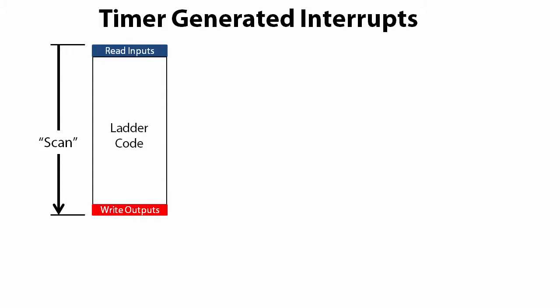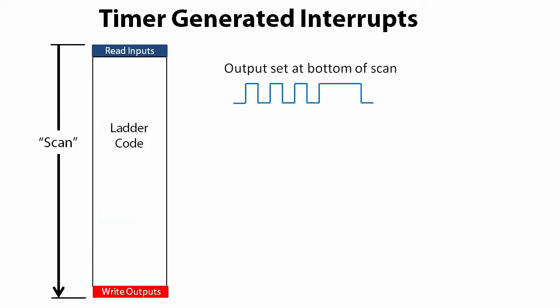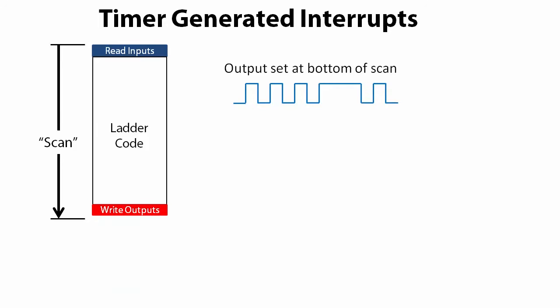If we toggle an output bit every scan, it will look like this on most scans, but on some scans it might take a little longer. It all depends on what the ladder logic is doing during that particular scan. And that's the key point - we never really know exactly when those outputs are going to be updated.